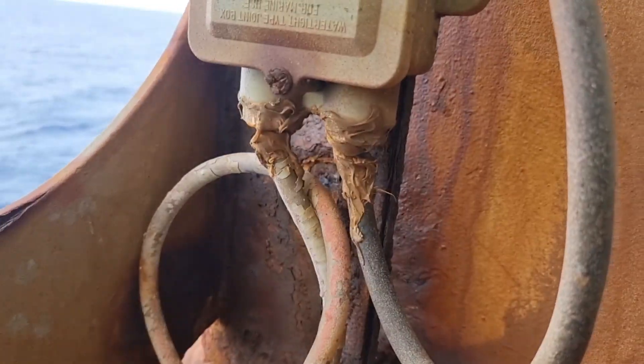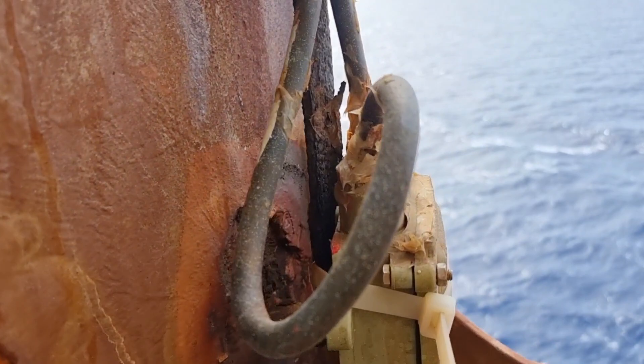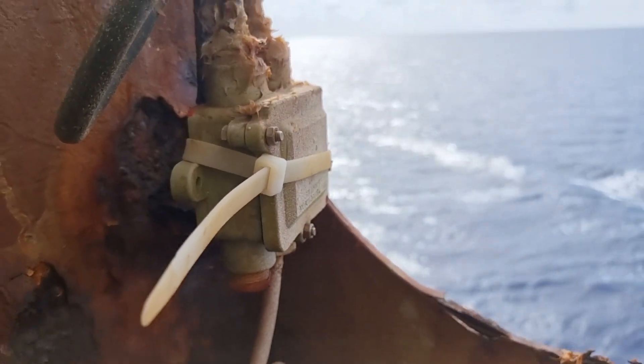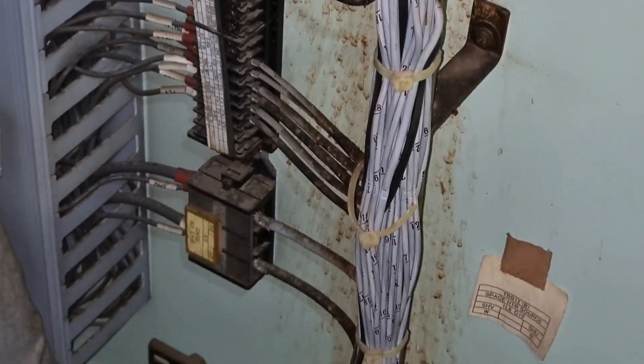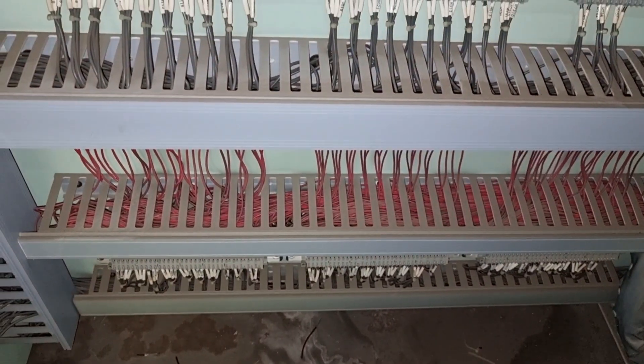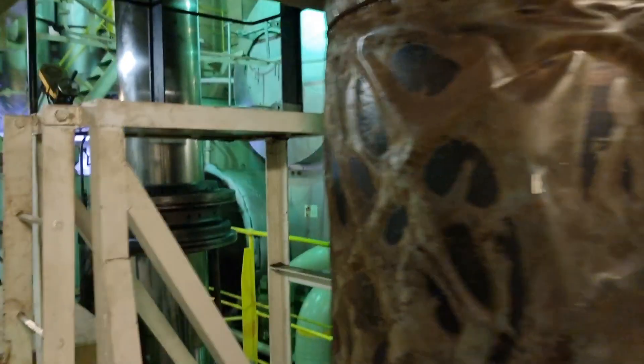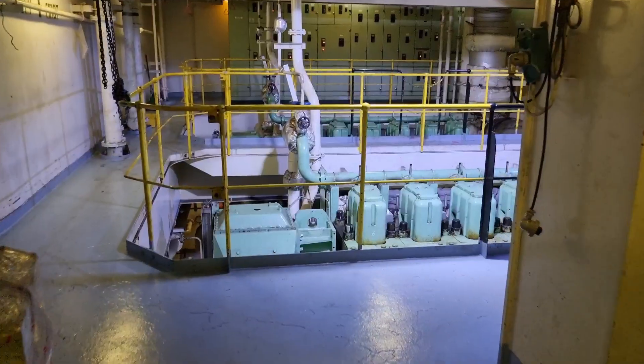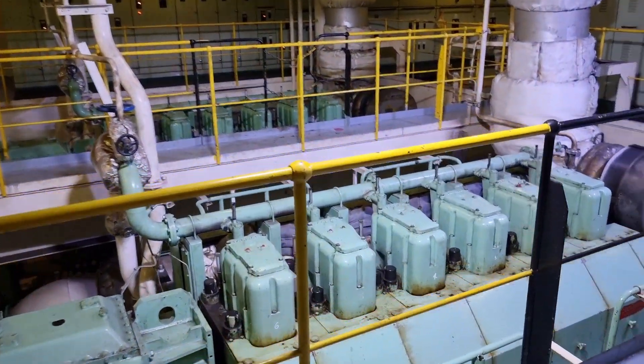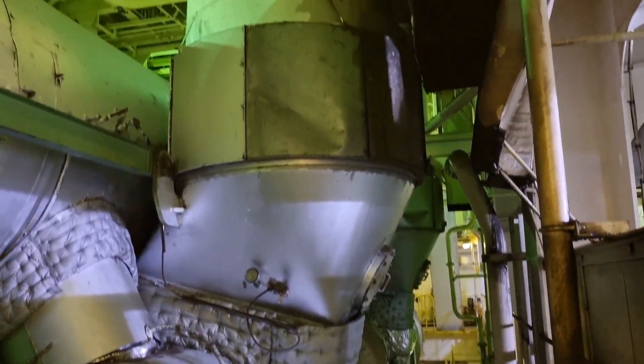There are a lot of reasons why we have earth fault on board. Some of these reasons is because of the weather, which leads to corrosion, or sometimes seawater goes into our junction boxes or even inside the wirings. Others are because of leakages that go into the wirings, which later break or become brittle. Based on my experience, most of the time the main reason for earth fault in the engine room is vibration.